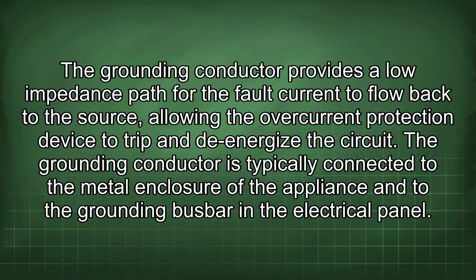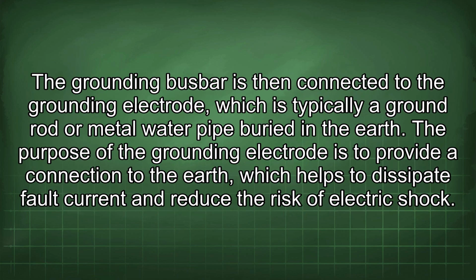The grounding conductor is typically connected to the metal enclosure of the appliance and to the grounding busbar in the electrical panel. The grounding busbar is then connected to the grounding electrode, which is typically a ground rod or metal water pipe buried in the earth. The purpose of the grounding electrode is to provide a connection to the earth, which helps to dissipate fault current and reduce the risk of electric shock.